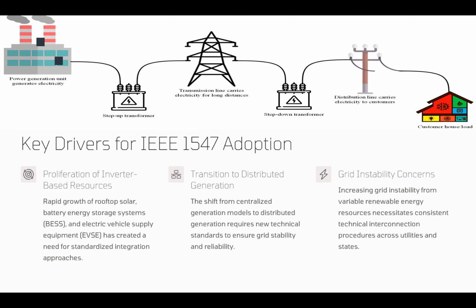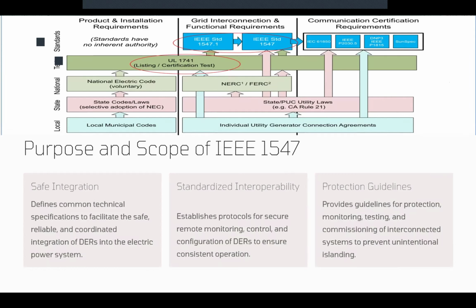Now, without any standard requirements to meet those challenges, every DER manufacturer uses different settings. And if we have different settings and vendor-based configuration, we have uncoordinated responses when we are dealing with those fluctuations or any disturbance in our system. Okay. Now, the IEEE 1547 introduces some ride-through requirements, like voltage ride-through and frequency ride-through. We are going to go deeper into those protocols. Or in the standard, some reactive power control, so it could help the DER to actively support the grid's voltage stability. Now, because of those reasons, this standard was developed.